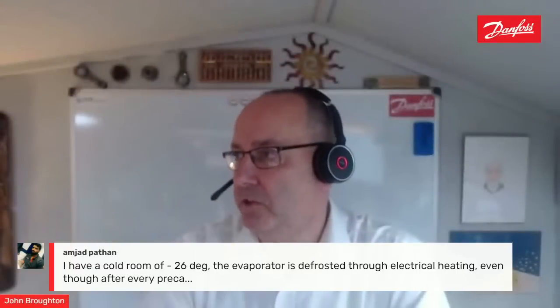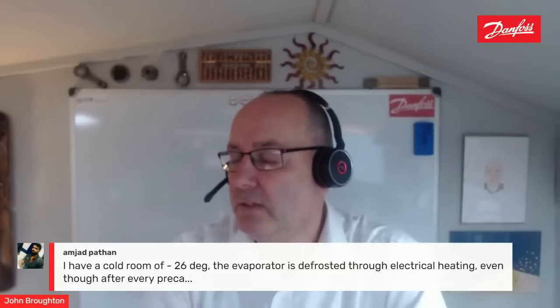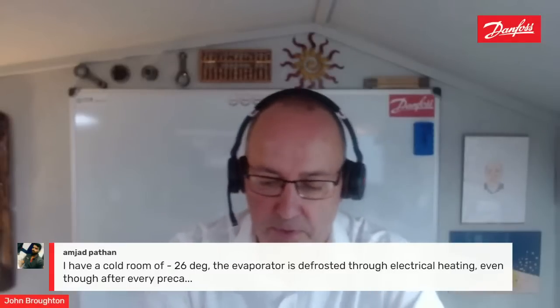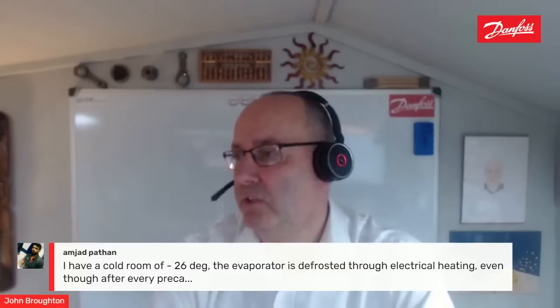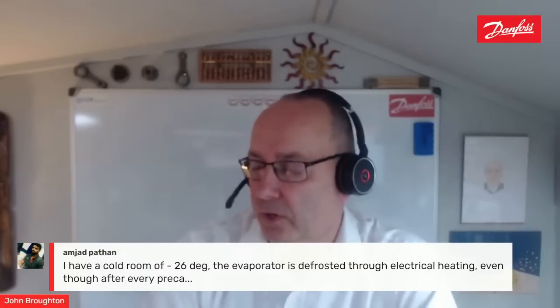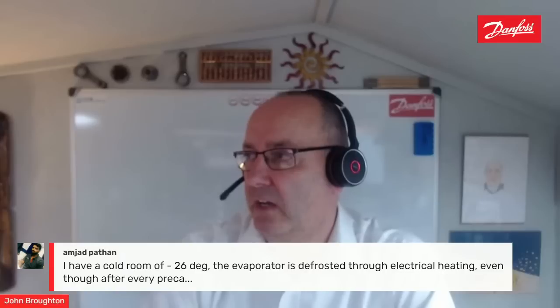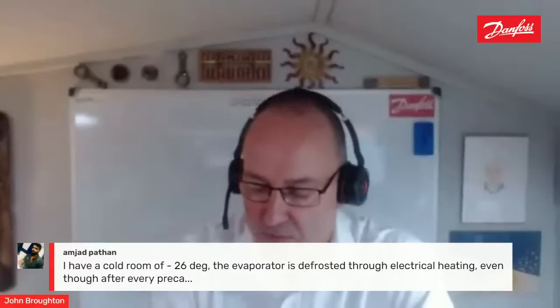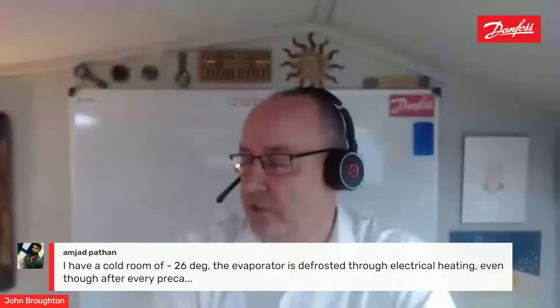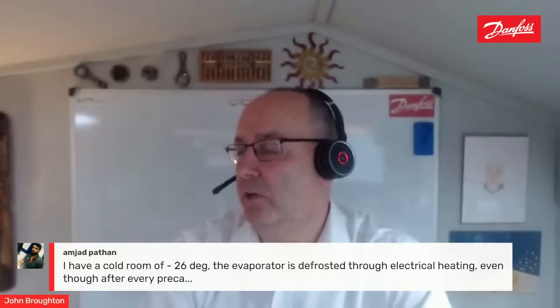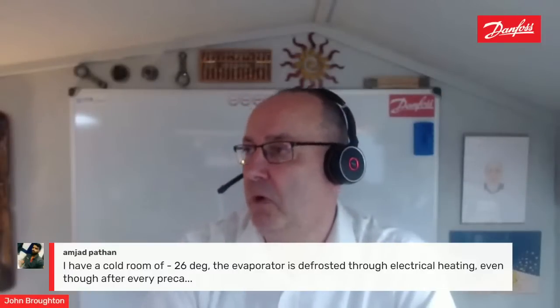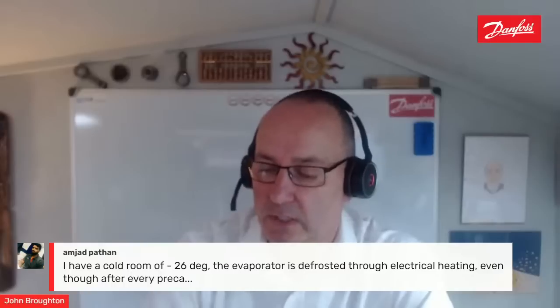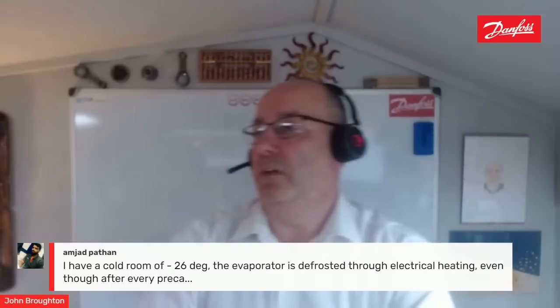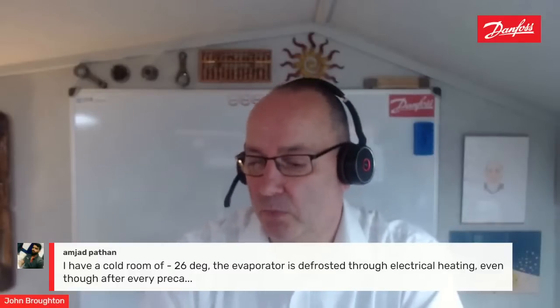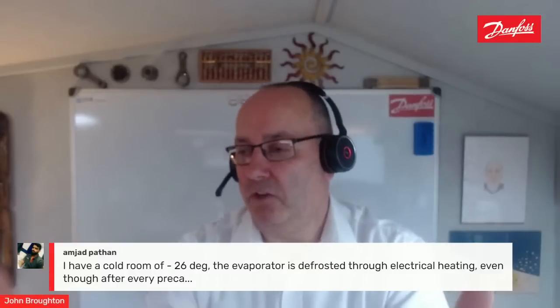It depends if they're on a defrost termination stat or whether they're on just timed only. So you can have temperature terminated with time and security, or just time terminated. It depends how long they are running for. You should need to run a defrost for a maximum of 20 minutes on a deep freeze. If it's any more than that, maybe look at how much frost is being accumulated on the evaporators, maybe airflow across the evaporators. Make sure that we're not boxing in that cooler with product. Make sure it's not above a doorway, things like that.